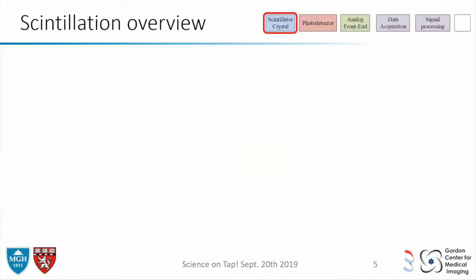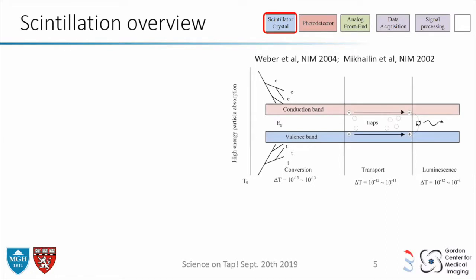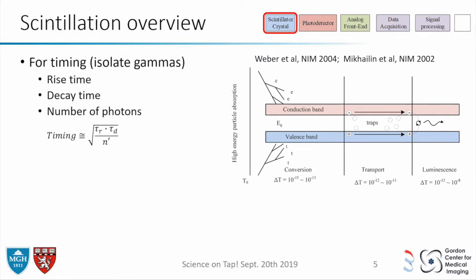Once the gamma comes in, it hits the atoms and gives energy to the electrons. They slowly come back to a stable state, multiplying along the path, and at the end you get about 20,000 light photons — that's not a lot. How fast can this be? It depends on the crystal materials, the rise time — how quickly it produces light — the decay time, how long it takes for the whole signal to be produced, and the total number of photons. This is useful for comparing crystals, especially for time-of-flight scanners.